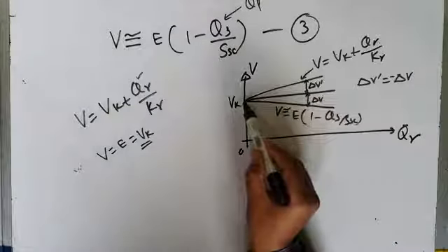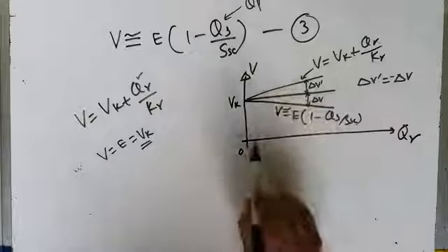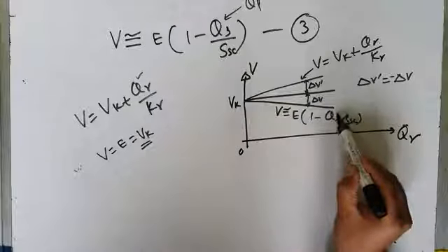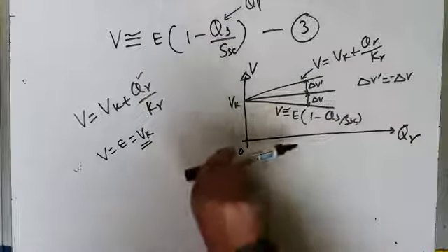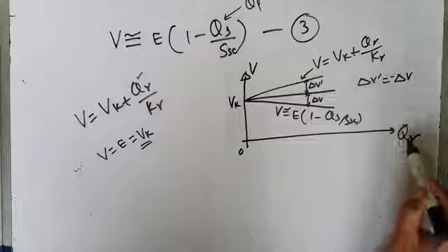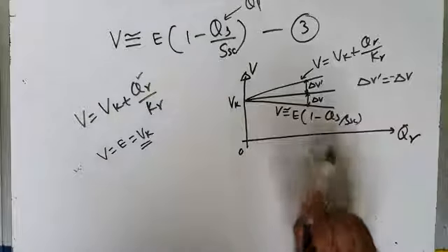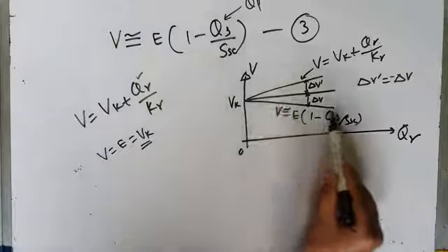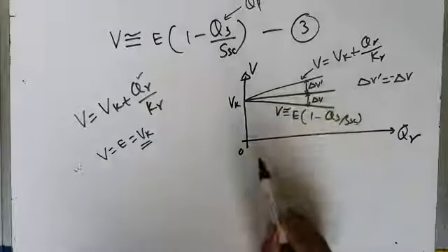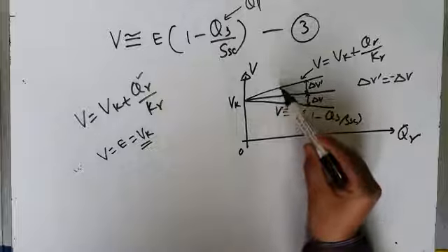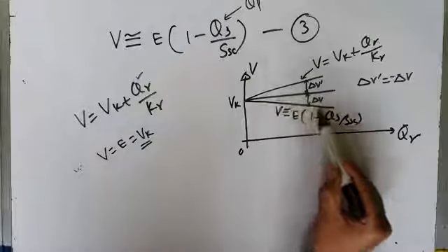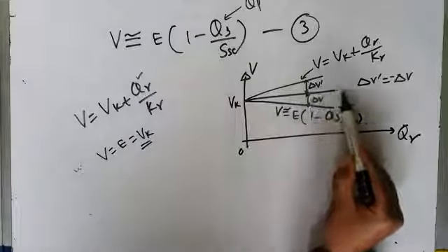So as the load reactive power increases, your compensator goes on injecting more and more reactive power, and hence to nullify or cancel the effect of the drooping characteristic, it tries to make the characteristic like this, and this characteristic plus this characteristic gives you the absolutely constant load bus voltage Vk.